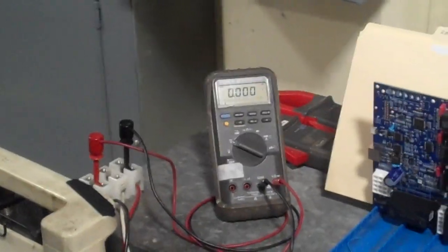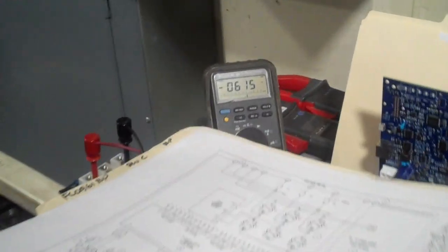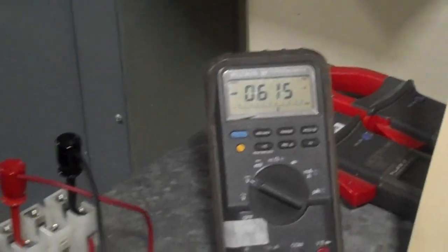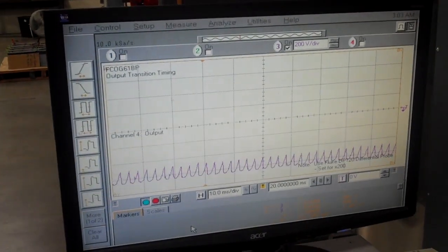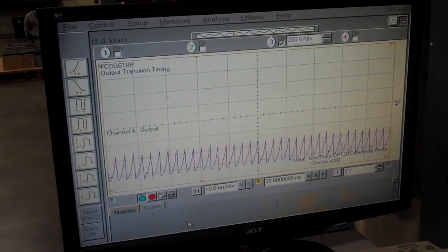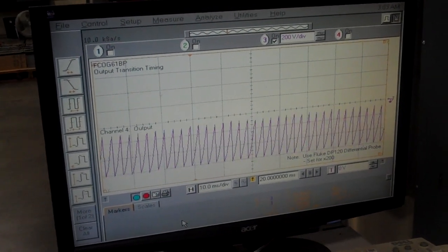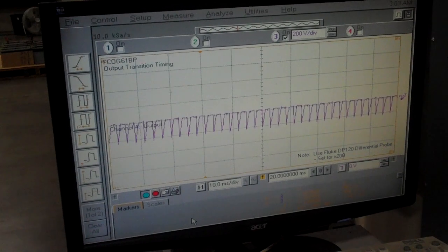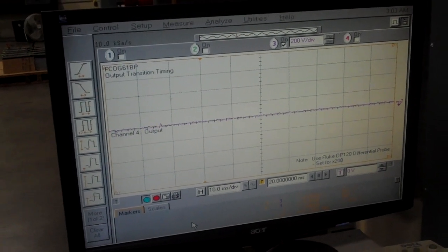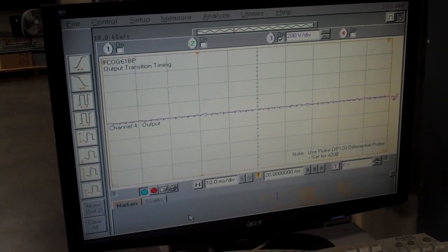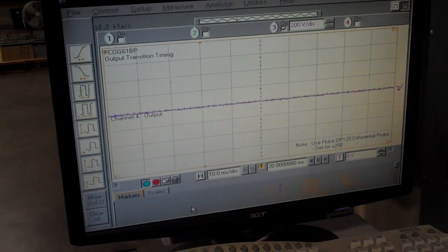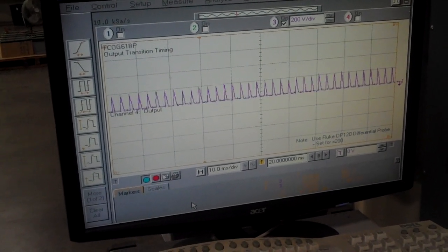So let's go ahead and enable, Tony. So there it is. Right now we have 615 volts DC. Do me a favor, Tony, can you start decreasing sig high, the enable command, from maximum from where you are to 0? So we see that it gets down to 0. Go ahead and transition polarity, and can you go back to 5 volts now on the opposite?